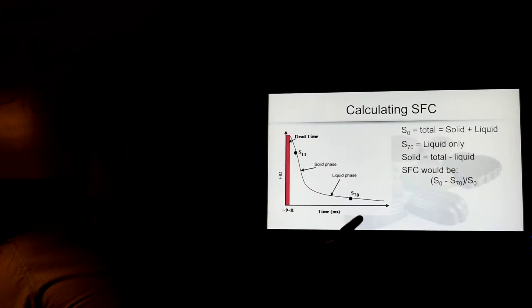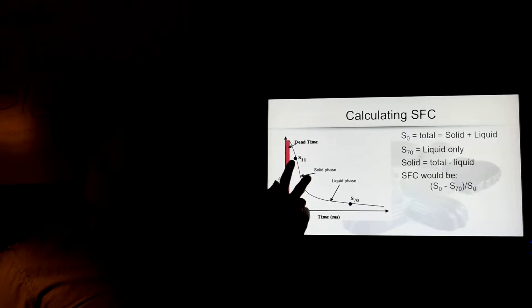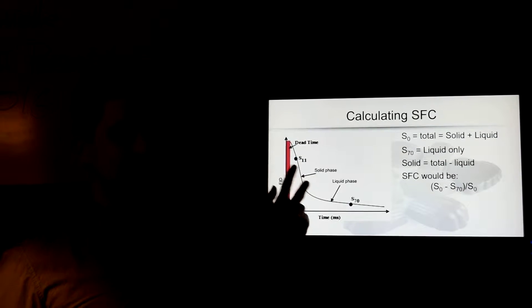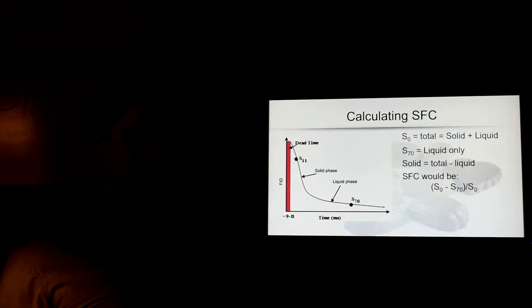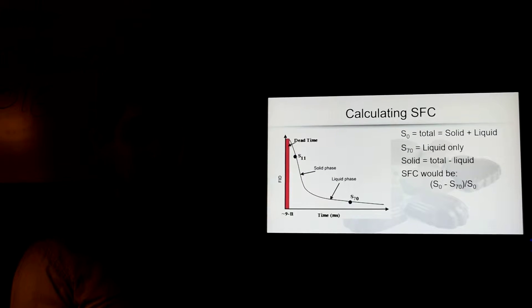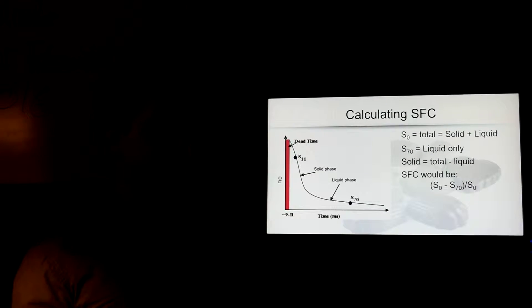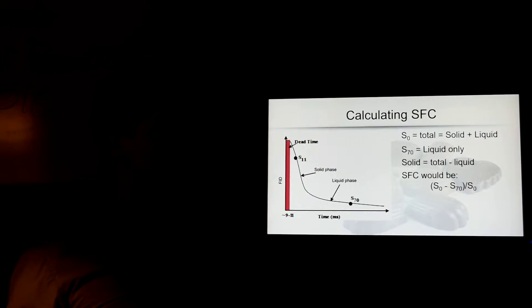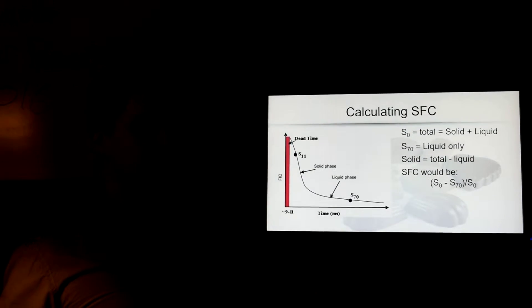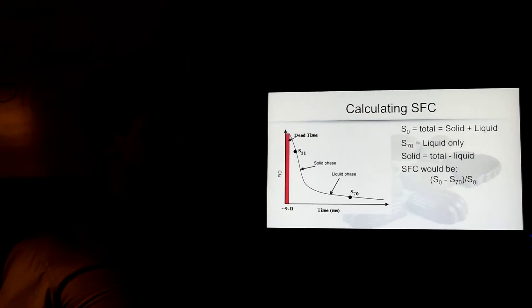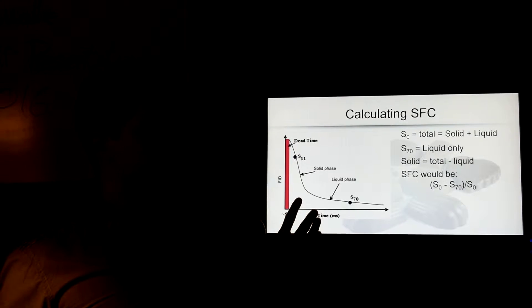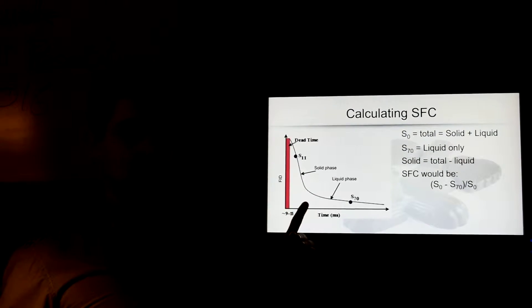We also have to add a correction factor at the beginning, because we can't measure the first 9 to 11 milliseconds. That's because when you hit your atom with the radiofrequency pulse, it gets stunned and kind of shakes around and resonates for a bit. So we start at about 11 milliseconds. To compensate for that, we're going to add a quick correction factor on the solids only, not the total.